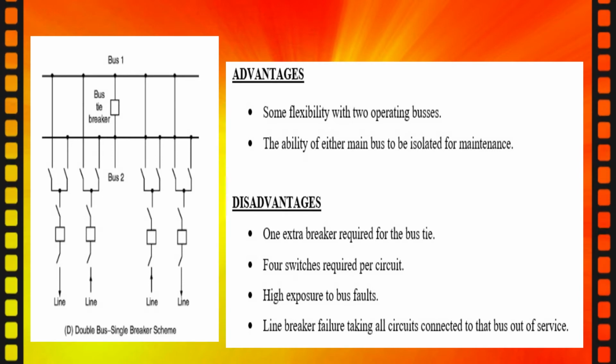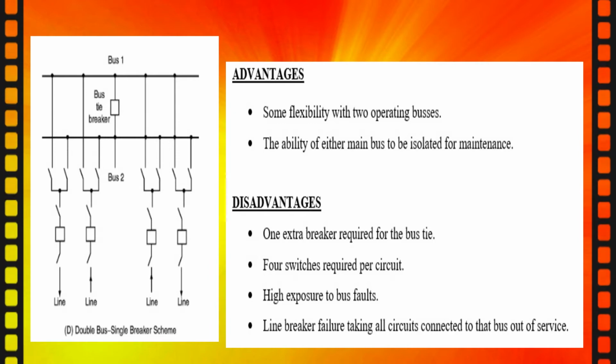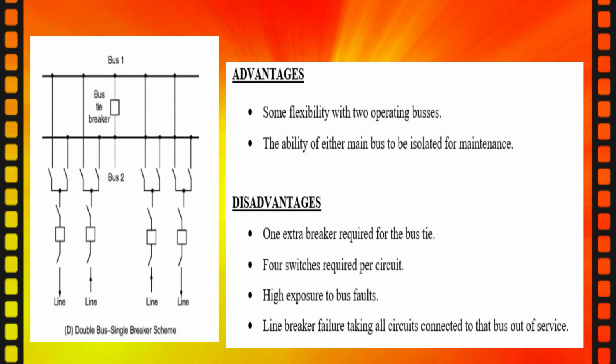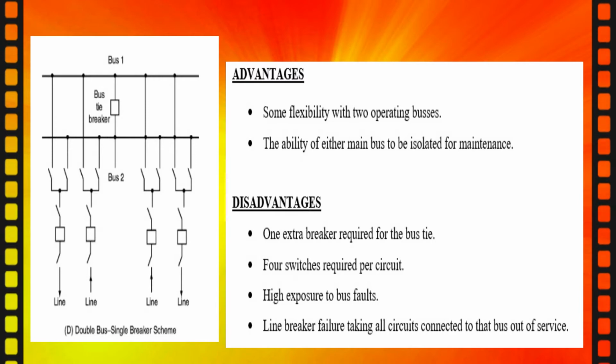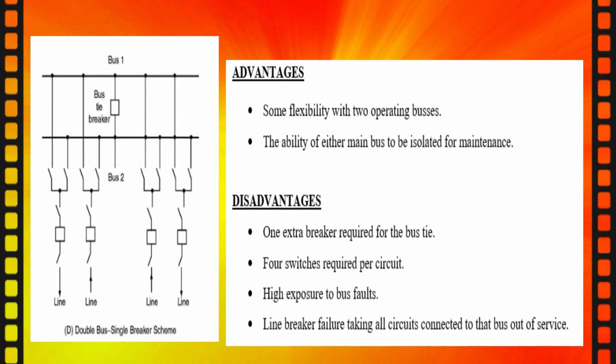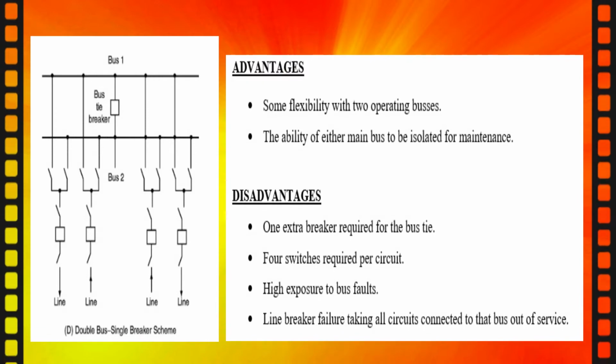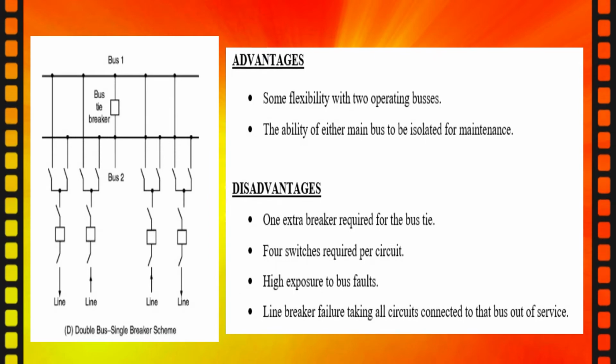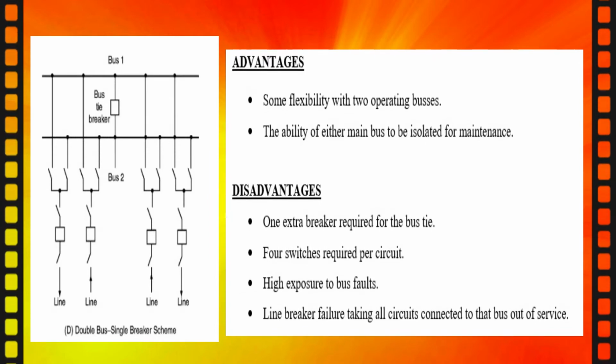Second, four switches are required per circuit. Another disadvantage is high exposure to bus fault. The line breaker failure also takes all circuits connected to the bus out of service.